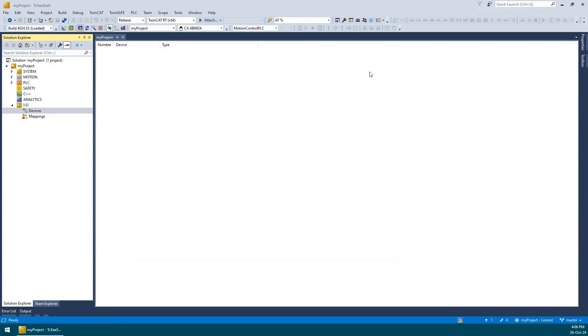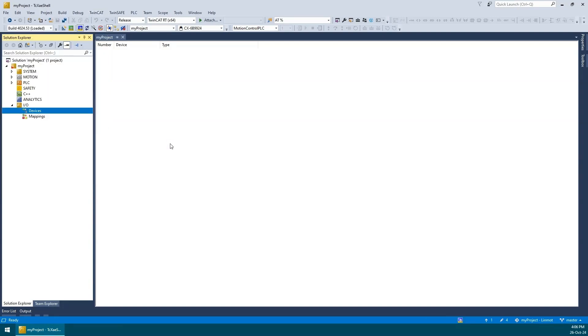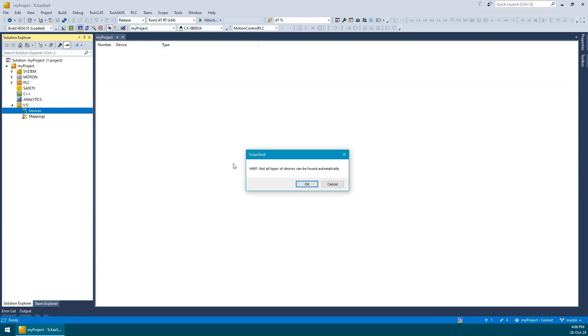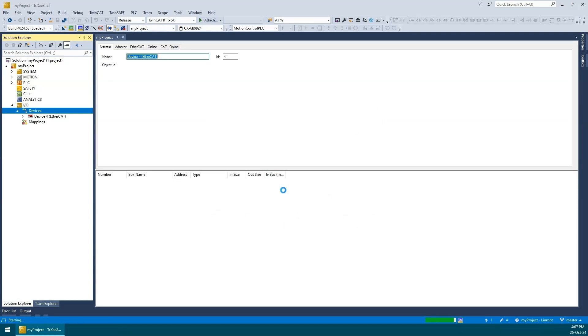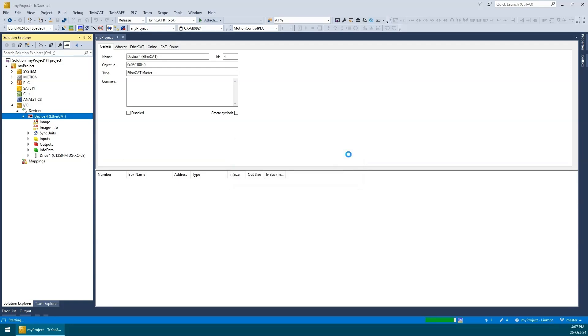Meanwhile, since the XAE only loads the ESI files on startup, I will now do a manual reload of the ESI files. Now I'll do an automatic scan again. This time TwinCAT recognizes the LinMot servo as a drive and is now asking us which configuration to use. Select NC configuration and press OK.